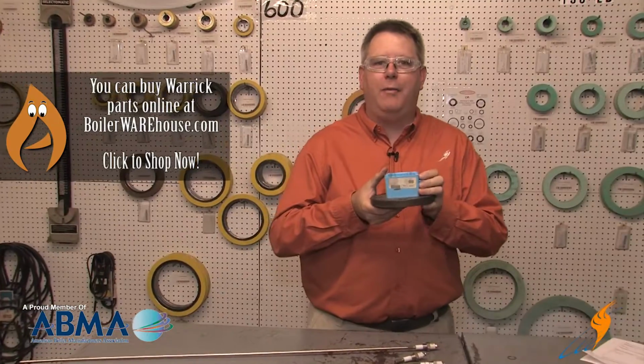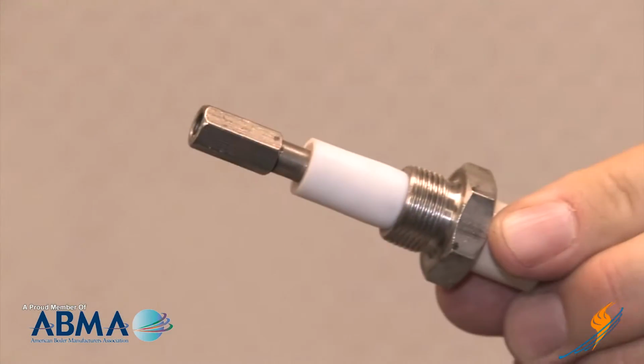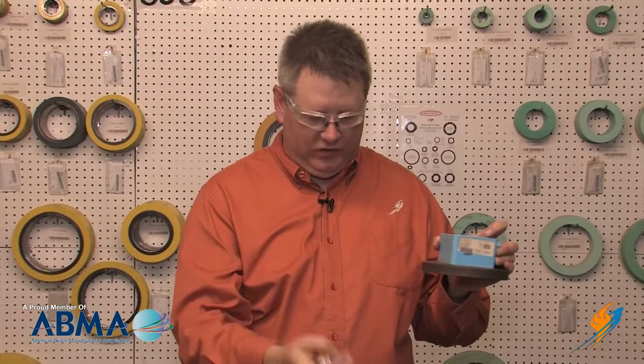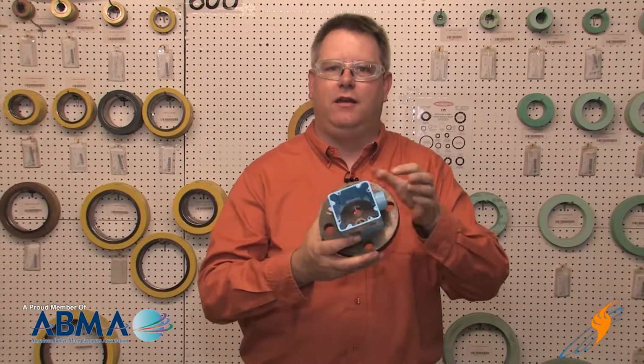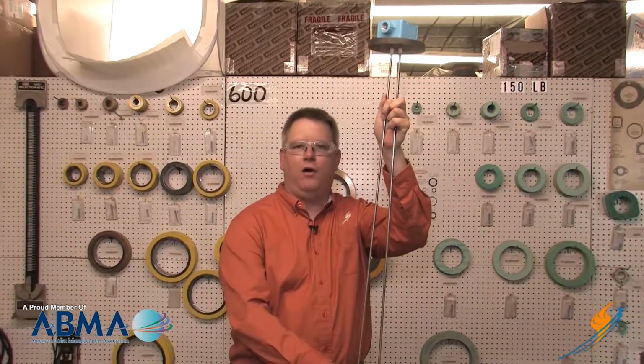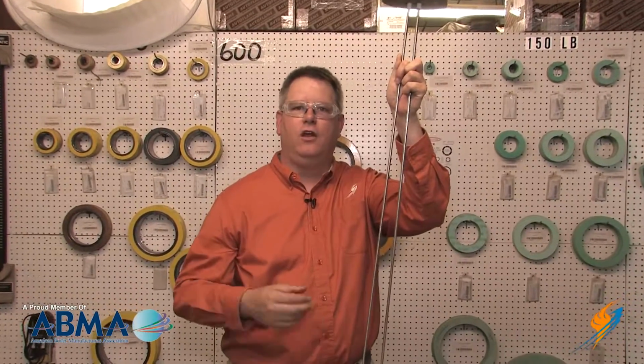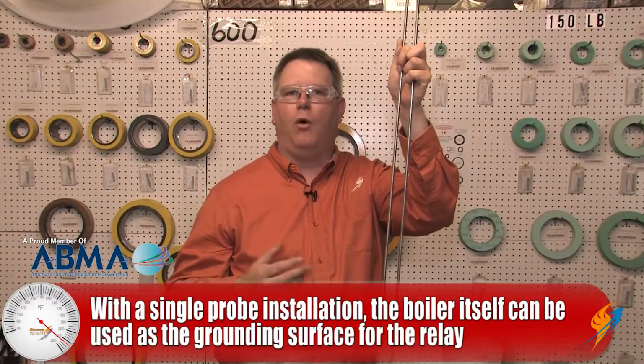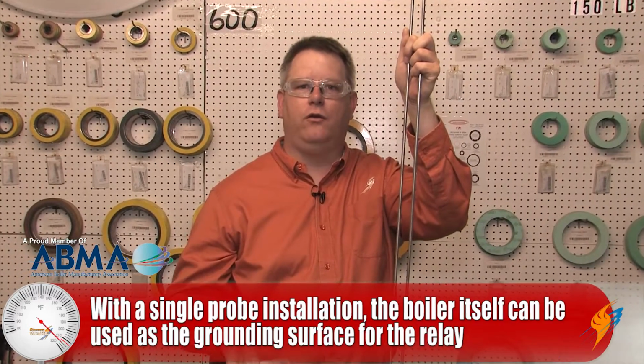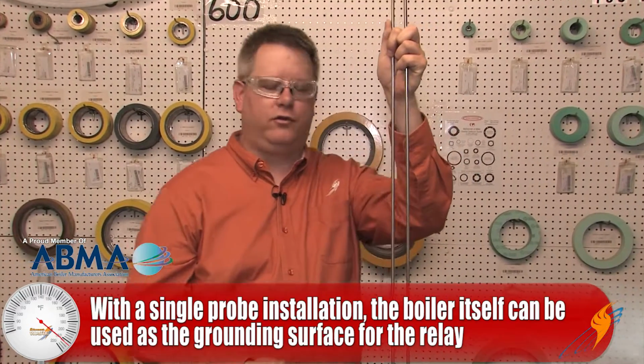This is a Warrick probe housing. Other manufacturers may have different thread connections on the probe devices. Warrick uses a machined thread, which is why we rely on the washer to make a seal, but some manufacturers will have a tapered pipe thread in both the fitting and on the electrode, so they're not interchangeable. Many times one rod will be used as a grounding surface. On a single probe installation, the boiler itself is used as the ground for the electrical circuit.